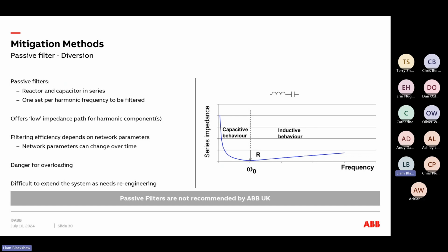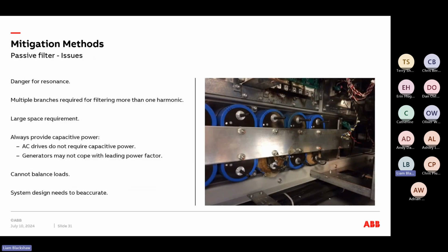So it's very difficult to extend the system, as it may need re-engineering. And we say typically ABB passive filters are not normally recommended, and I'll explain why in the next slide or two. But we've got a couple of examples there in a diagram, a nice little circuit diagram to show you what a passive filter system looks like. And when we say we don't normally recommend it, it's that passive filters can in some cases be difficult to design to operate in a system, as you really need to know well the system setup. And if, as I said before, that system changes at all, then the filter will not operate as designed. In some cases, those capacitors start to overheat, and in some cases have been known to set on fire, at least anyway.